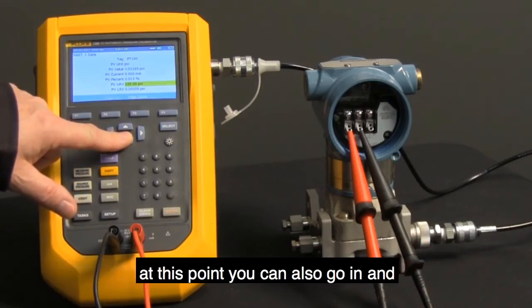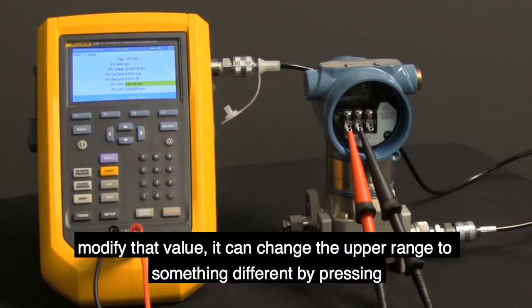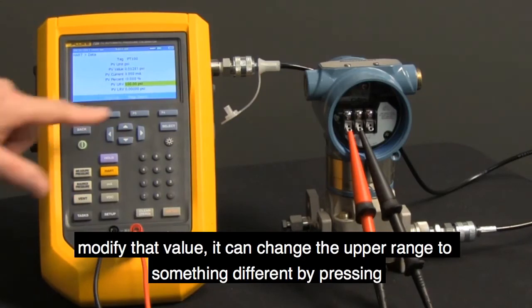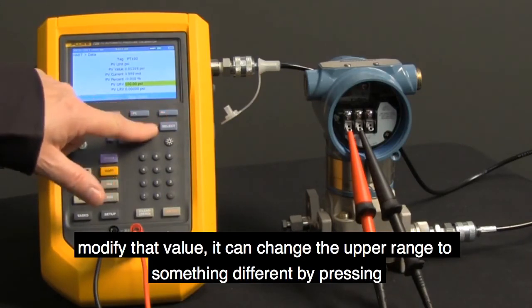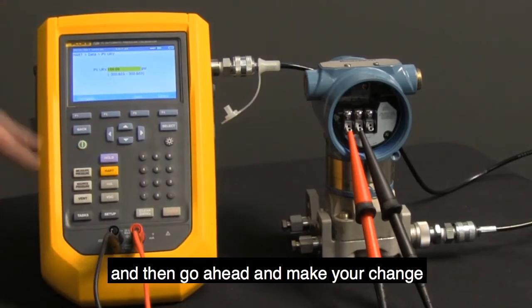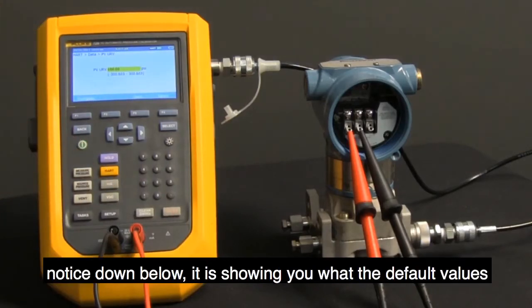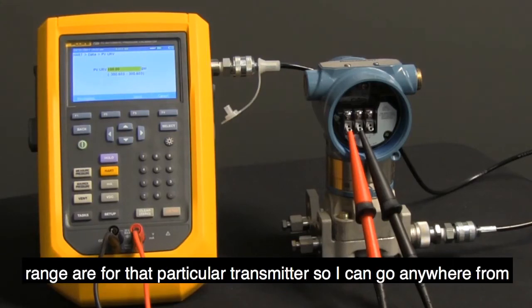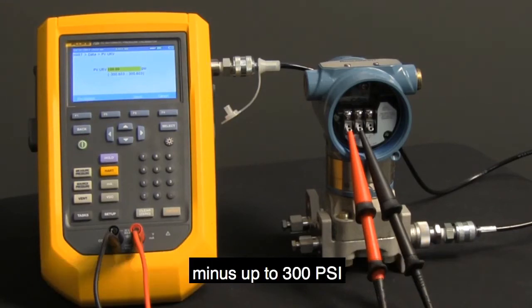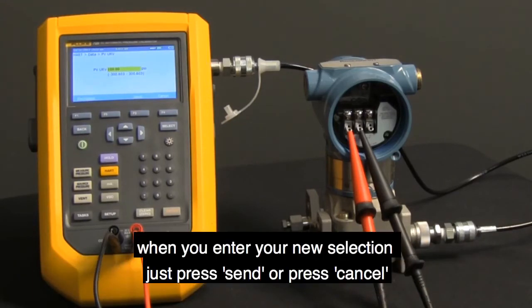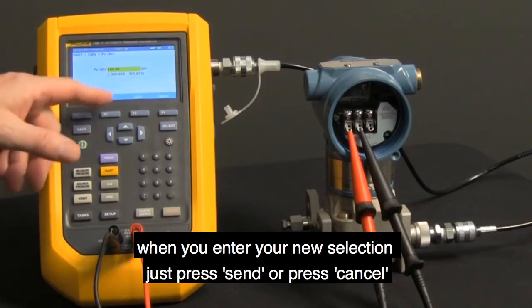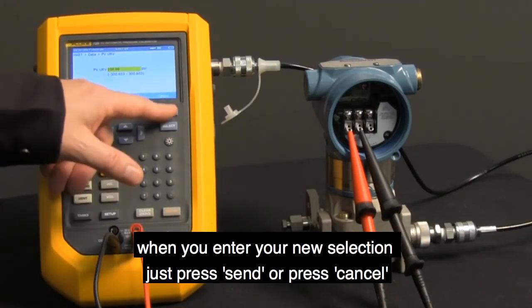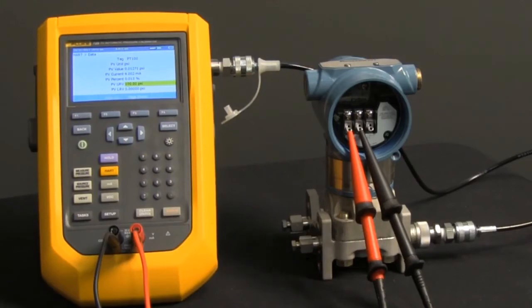At this point, you can also go in and modify that value—change the upper range to something different by pressing enter, then make your change. Notice below, it shows you the default value range for that particular transmitter, so I could go anywhere from minus up to 300 psi. When you enter your new selection, just press send or press cancel to go back.